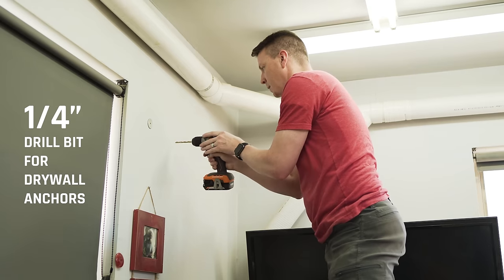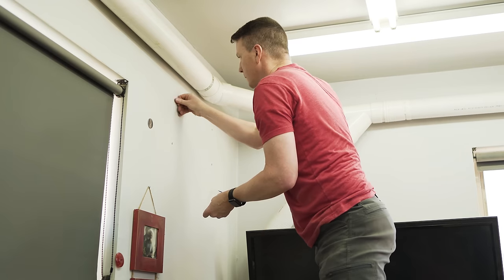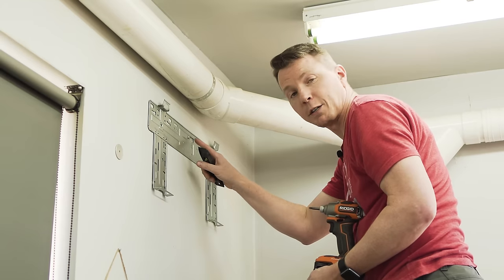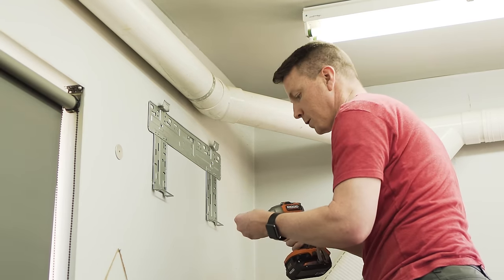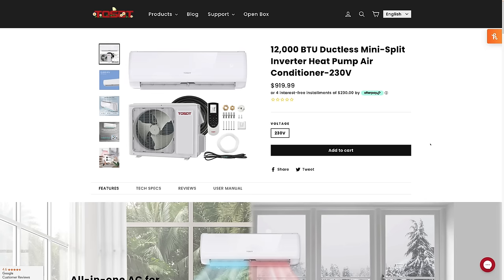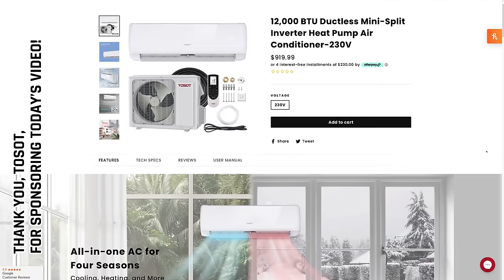I'm going to use a quarter inch drill to drill the holes, then tap in the included drywall anchors. Once you've got your first screw in, it's a good idea to make sure everything is level right there. Then you can secure the others. The instructions I'm showing here are applicable to just about any mini split on the market, but the specific unit I'm using is made by Tosot — a 12,000 BTU unit.